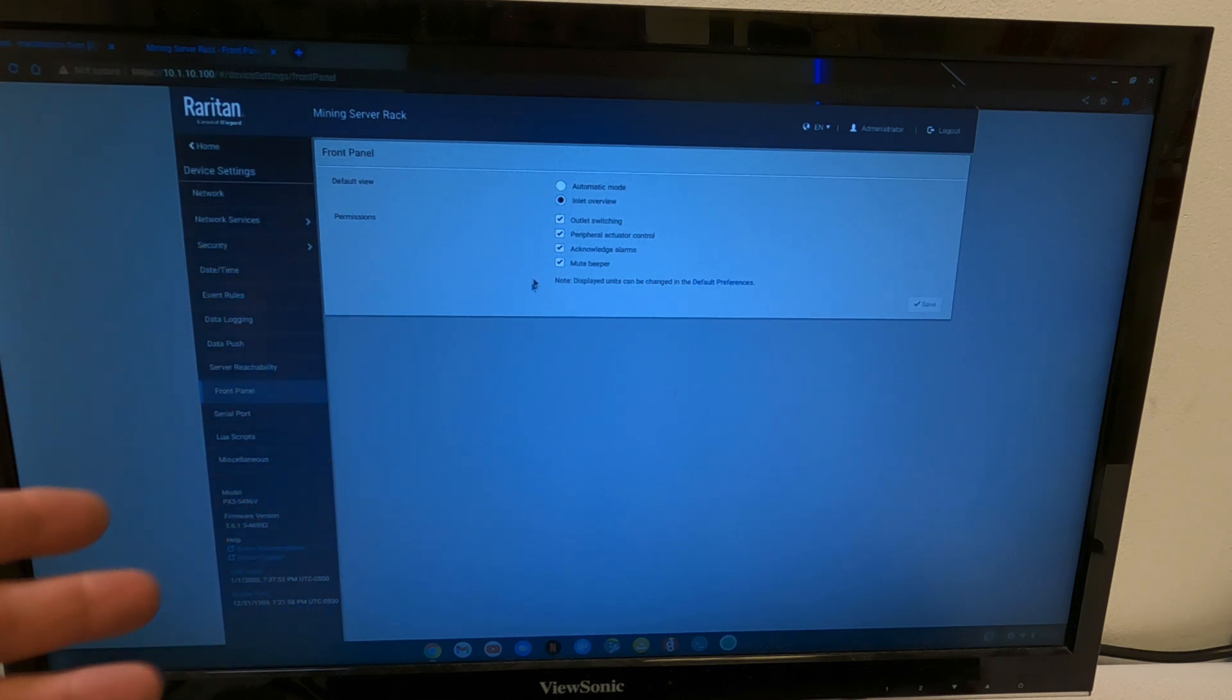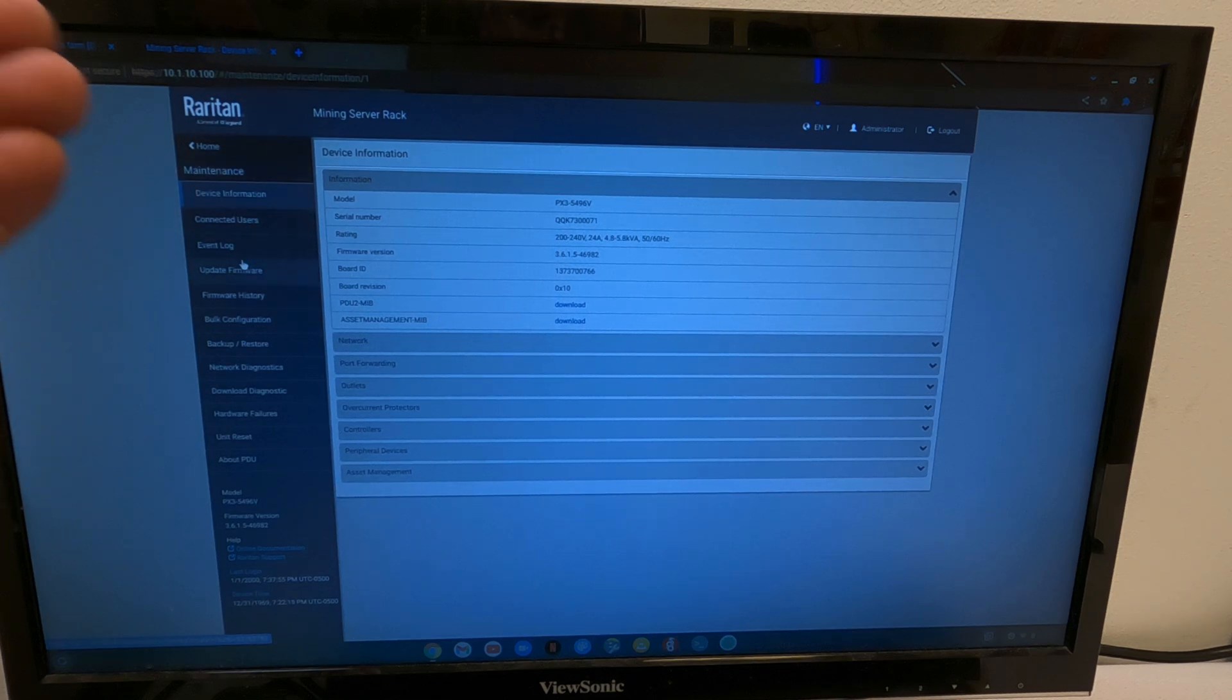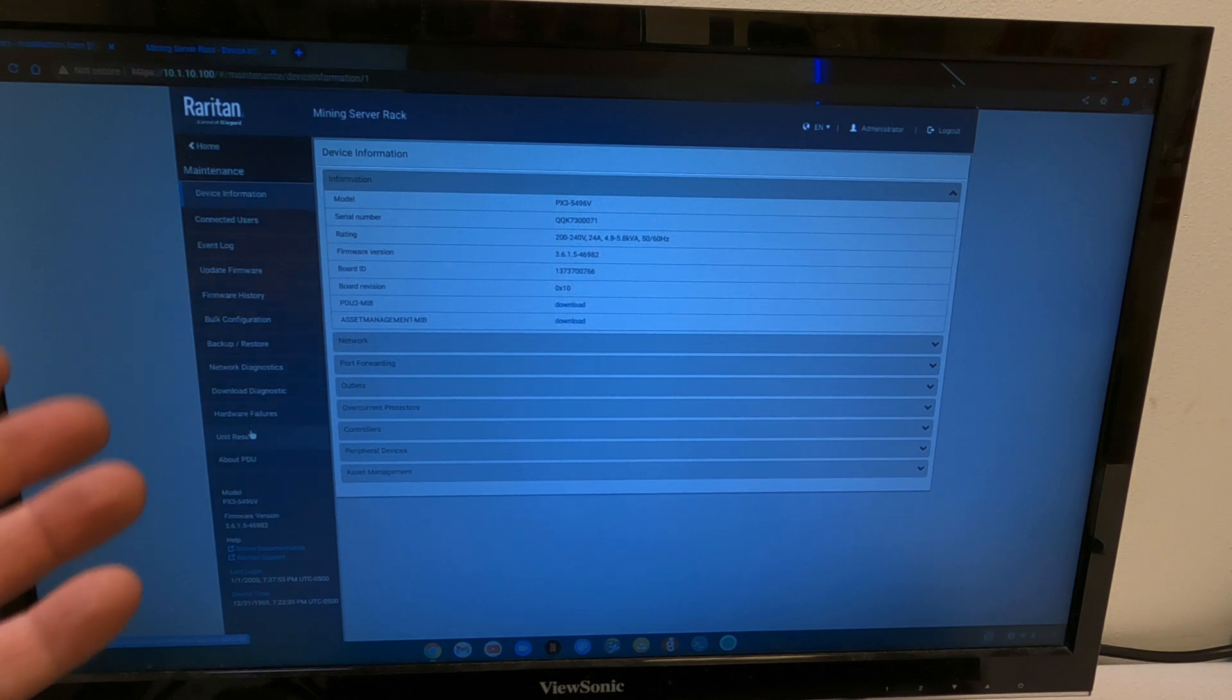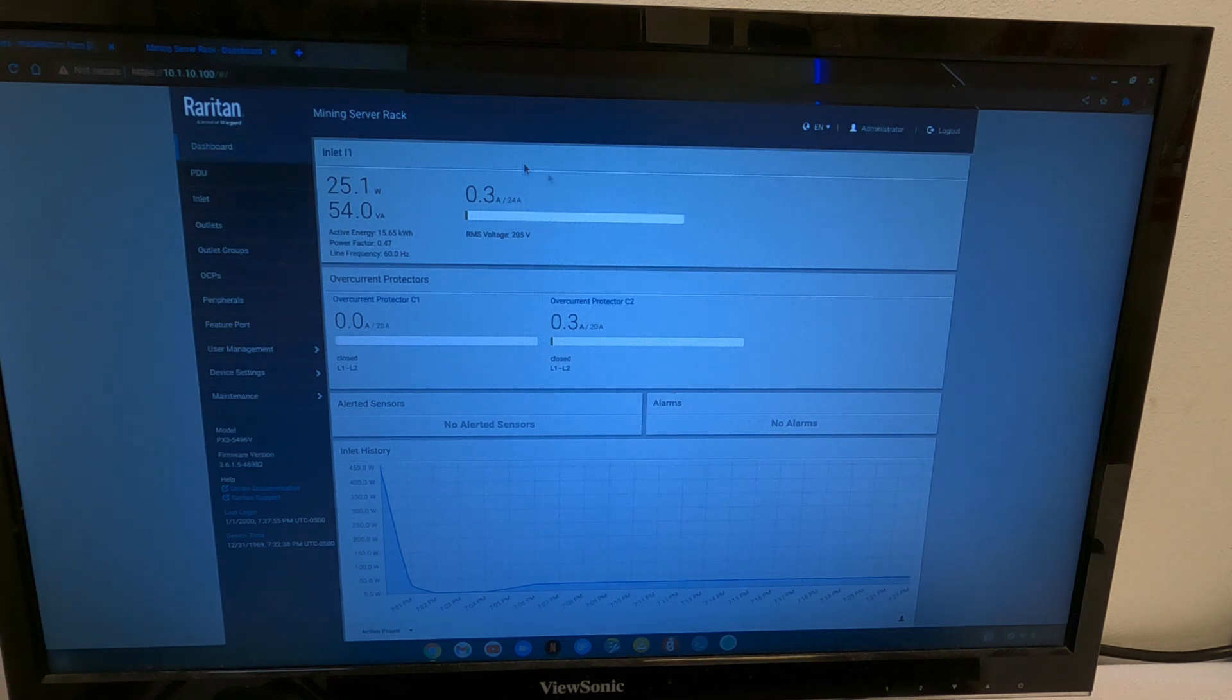Then, we have user management. Right now, all I have is the admin, and you are not going to find out my password. You can even change some of the parameters that normally show up on the front screen of the display itself. Then, even under maintenance, you have connected users, event log, you can update the firmware for the brains on the PDU, firmware history, backup and restore your configuration, network diagnostics, hardware failures, full unit reset. It's insane how much information you can get out of a smart PDU.